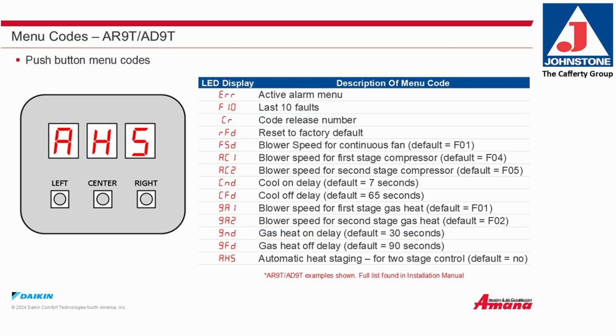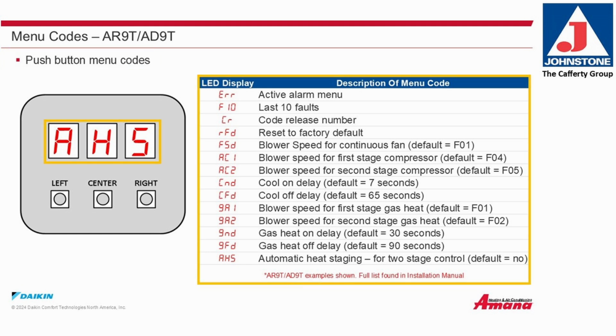Menu codes. Here are some of the push-button menu codes. ERR, active alarm menu. F10, last 10 faults. CR, code release number. RFD, reset to factory default. FSD, blower speed for continuous fan, default F01.